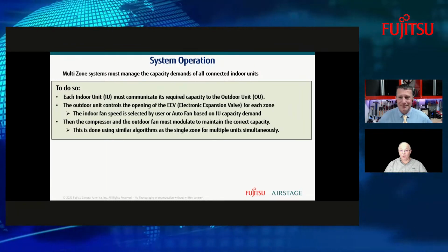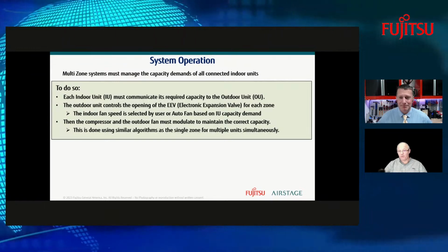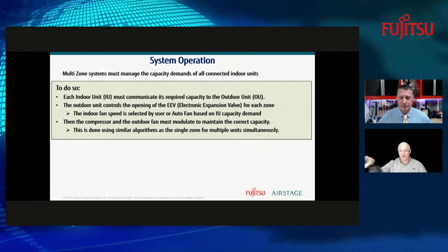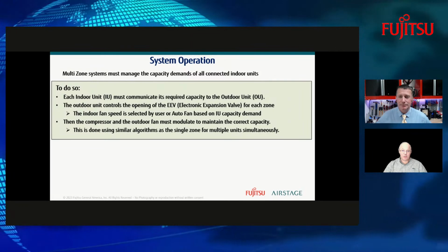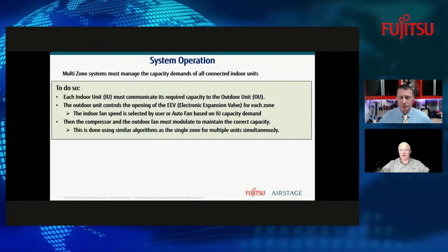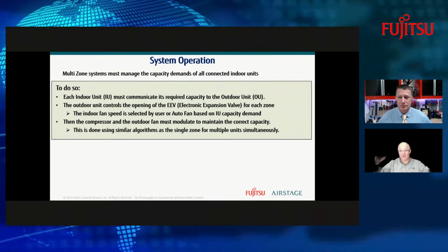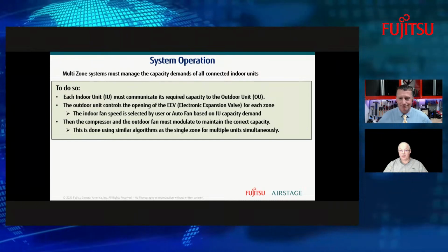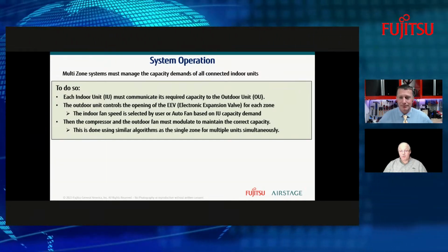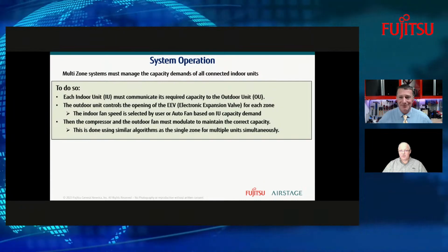So I need even more refrigerant so I can send some additional refrigerant to that indoor unit. So I've got to open up that EEV. Well, I need to speed my compressor up to this level and my outdoor fan to that level. And that's the beauty of multi-zone. It's one of the most perfect zoning systems you'll ever install.